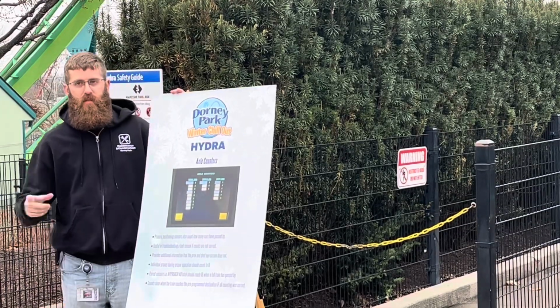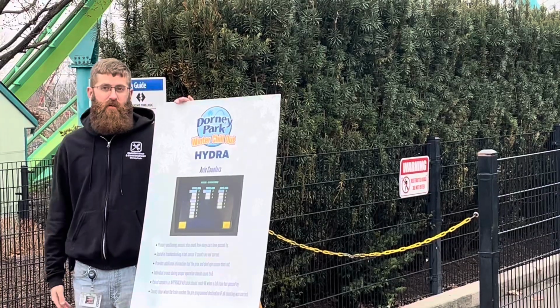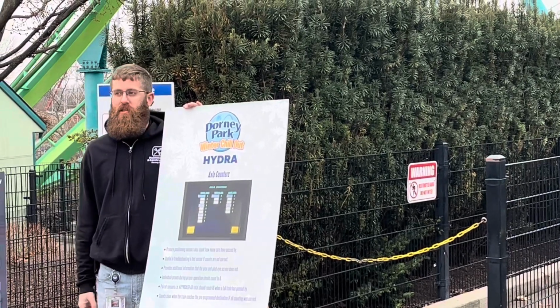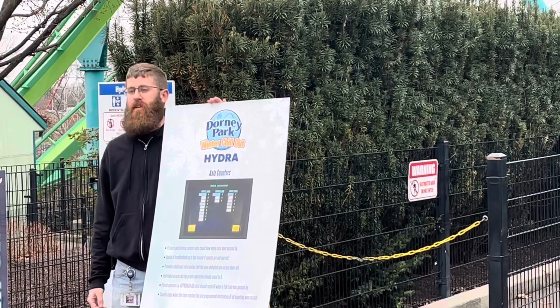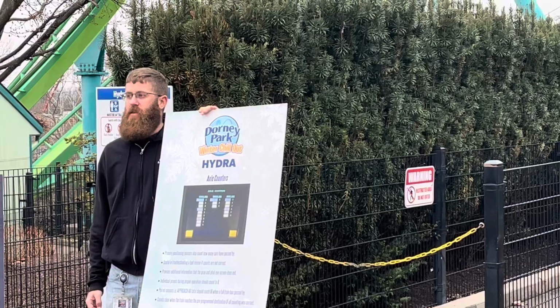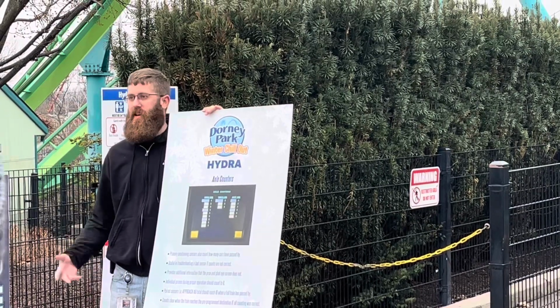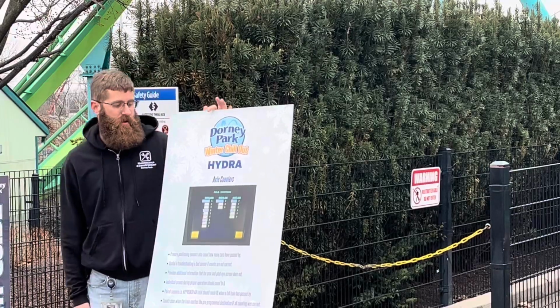And that's one of the reasons why when there is a stoppage, sometimes it seems like it takes a while to get the ride restarted. Depending on what the issue is, we try and go through as many of these screens as we can, because sometimes, especially on an intermittent problem, the only time to really get the information you need is when it happens. And if it's not going to happen for another 2 hours, you're just not going to make any headway. But that's important to know about the axle counter screen.